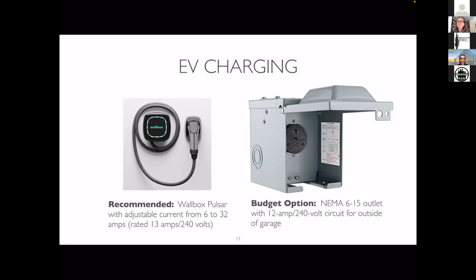Another thing Tom and I employ when electrifying on an existing panel are devices that let you share a circuit smartly, and also pause a circuit if, for example with the DCC9 here in the middle, the total load in the house is above a certain level. So you could set it to say, if my house is on a 100 amp panel and using 80 amps, shut off my car charger — that's what the DCC9 does. Very useful. A simple switch would just let you plug both your EV charger and your dryer into one 240 volt circuit. In this case, it's hardwired.